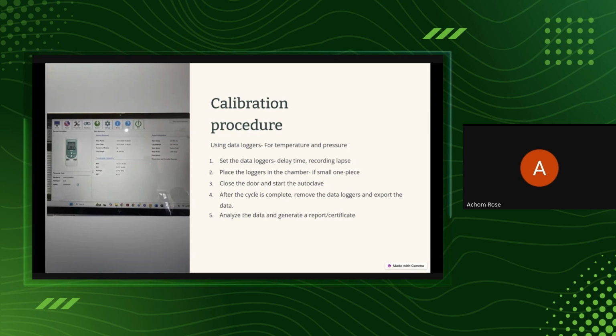So here, you as the person who is calibrating, you're going to record when the sterilization time started. Maybe it started at 3:15. So when you're downloading this data, you know that from 3:15 onwards, that was the 121. That's when the autoclave was supposed to have attained the 121. Okay, so you analyze this data and generate a report. So that is for the data logger.